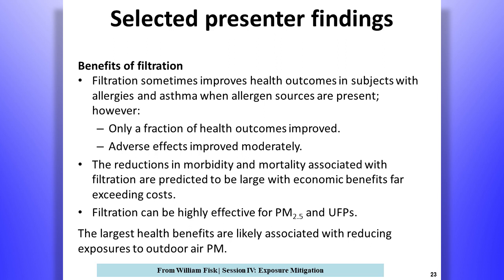And for our international participants, there are three systems currently in use in the United States that are used to rate filters. One of them, colloquially known as the MERV, Minimum Efficiency Reporting Value, was developed by ASHRAE. It rates filters on their minimum efficiency within a set of particle size bins. Another one is the Microparticle Performance Rating, or MPR, which was developed by 3M. It rates performance on removal of particulate matter in the 0.3 to 1 micron range of size.